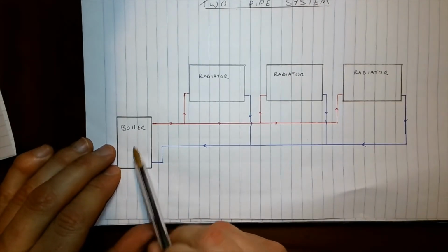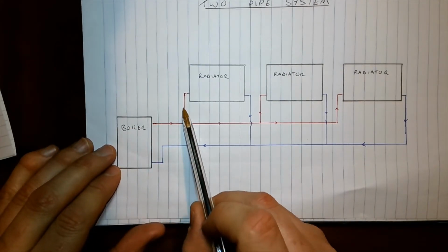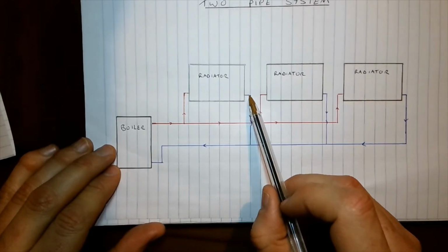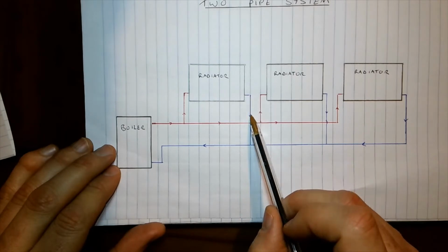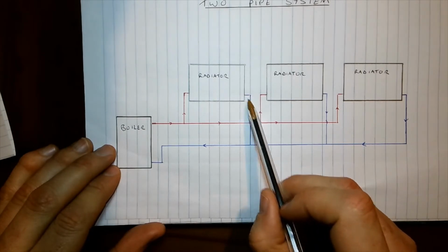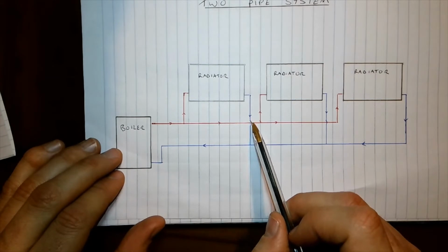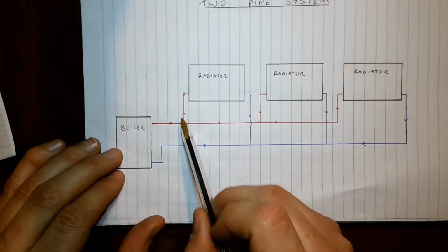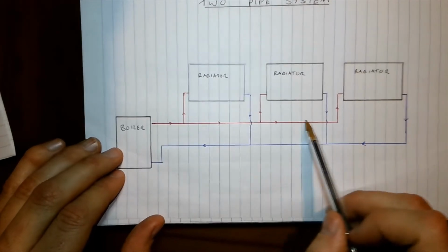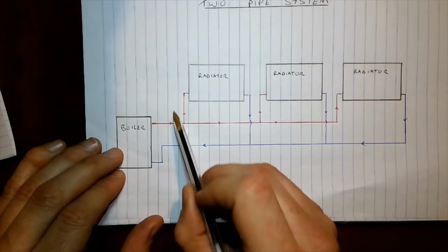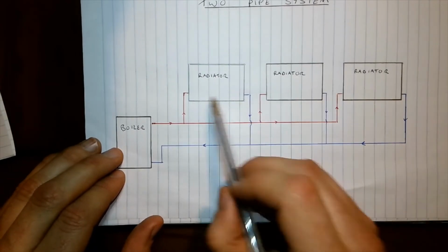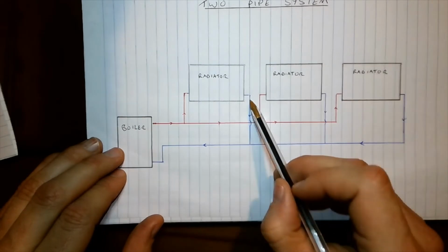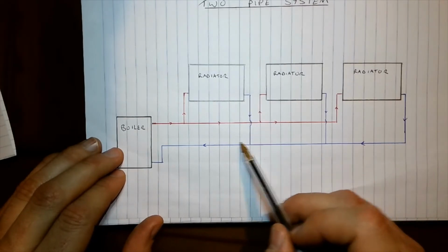The water is heated in the boiler, the hot water comes out, it goes into the first radiator, heats up this radiator, the cooler water comes out, and there's a second piping system, that's why it's called a two pipe system. It comes out, goes around that, and comes straight back there. So the hot water goes up in there, and up in there. Basically the hot water coming out is going into each radiator evenly, and as it networks its way through, when it cools, it doesn't go back into the hot water pipe, it bypasses that, it's a second pipe, and it comes back in.